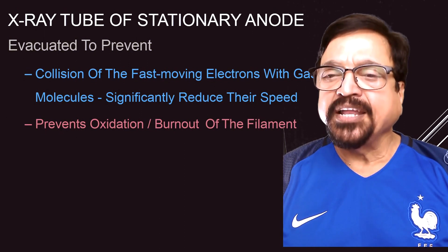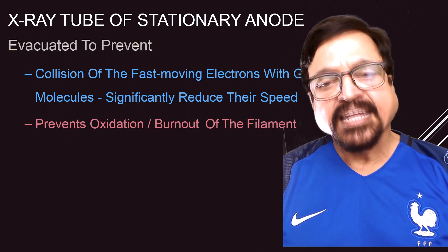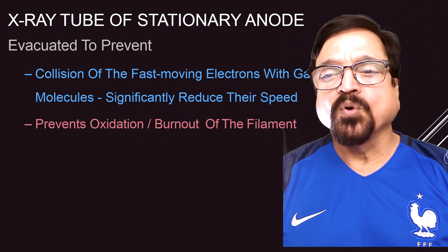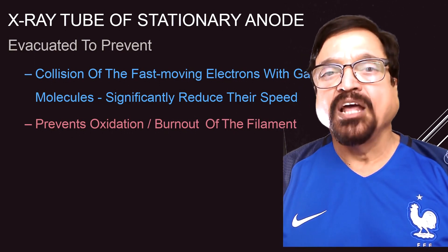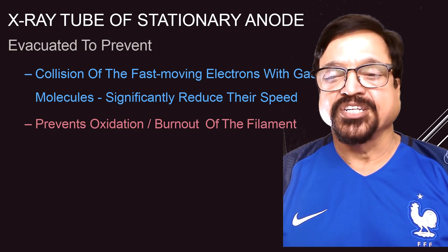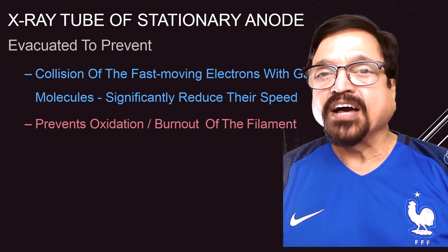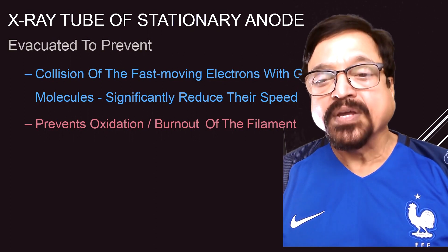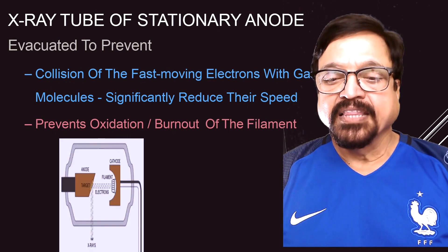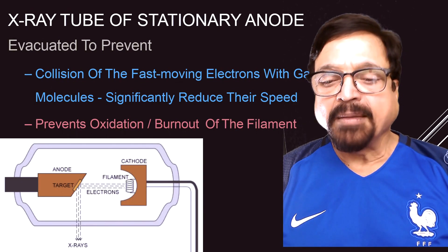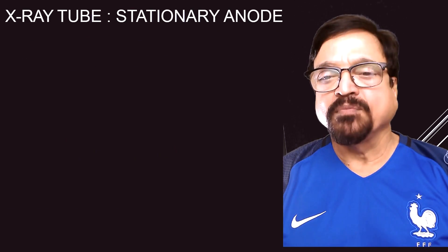The X-ray tube of the stationary anode is basically an evacuated glass envelope or glass tube. This is because if there is gas, its molecules will collide against the fast-moving electrons. Also, if there is air, the oxygen present would cause oxidation or burning of the internal structures. Therefore it must be a glass envelope that is totally evacuated. There will be no hindrance to the fast-moving electrons since there is no gas, and they will have steady acceleration with no reduction in speed. You can see the target cathode and filament from where the electrons are liberated and bombard the target to produce X-rays.